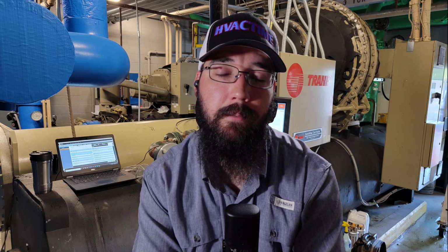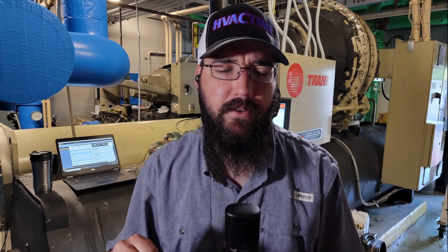With a lot of your air cooleds, even if it's a 400-ton machine, it's multi-circuit. So you also have to think about that. Even a 400-ton machine may be two 200-ton circuits, or it may be four 100-ton circuits. And that's how they're able to continue using a single valve head, and it may be economical to just scale that valve head up. Now, that's to say that they didn't do a multi-stack valve. And actually, I should have got a picture of this. I didn't think about that.